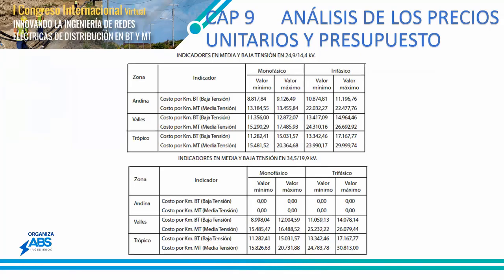Esta es una tabla del Viceministerio de Electricidad de mi país, que nos da valores aproximados que podemos manejar. Generalmente, un alcalde de algún municipio nos puede preguntar: necesito hacer el montaje de una red eléctrica de 10 kilómetros — ¿cuánto puede costar? Con estos indicadores podemos darle un pantallazo de cuánto puede costar una red eléctrica, ya sea en 24.9 kV, en 34.5 kV, monofásica o trifásica.